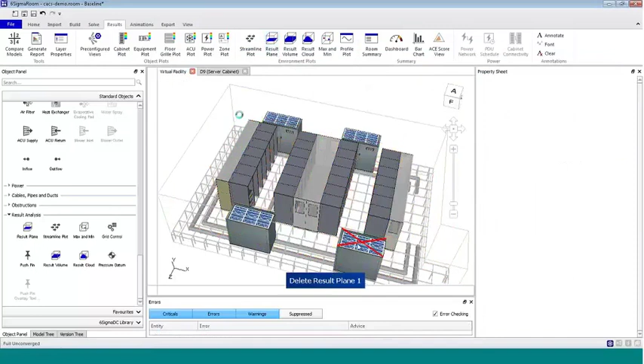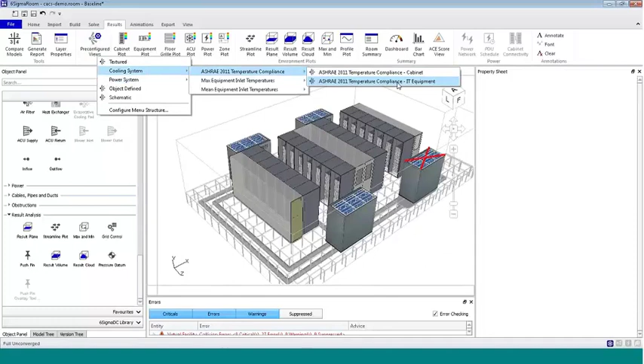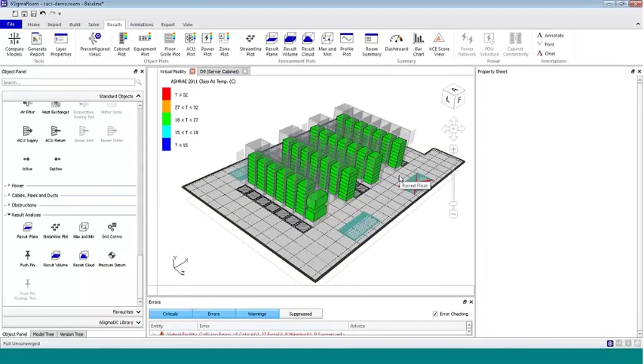A lot of people are also interested in looking at the temperatures inside the cabinet. So we've implemented ASHRAE compliance. Because we're so data center focused, we provide the best tools to analyze the temperature of every individual piece of IT equipment, using ASHRAE temperature standards defined at the IT equipment level. You can see all the IT equipment is now colored green.